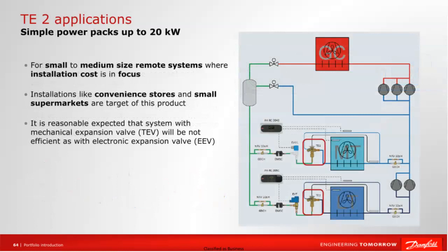Another application in which a thermostatic expansion valve can be used is small and medium-sized centrally supplied systems where the key factor is the investment cost. The product is dedicated to installations such as convenience stores and small supermarkets. It is worth noting that in the case of systems with a thermostatic expansion valve, TEV, the efficiency will not be as high as in the case of electronic expansion valves, EEV. It is important to understand this difference, especially when choosing the right technology for a given application.